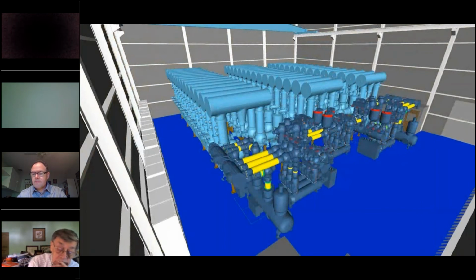If you need more precision, you can go to certain areas and get a little bit closer. For instance, with gas insulated switchgear, the tolerance is extremely tight. So at the interface where new and old equipment connect, we need to have extreme precision. And so that's just a function of how many scan setups we do and what particular device we use. But in this particular case, we had an existing switchgear in light blue color and an extension in dark blue, which was by the same manufacturer, but it was newer equipment. It was a different footprint.